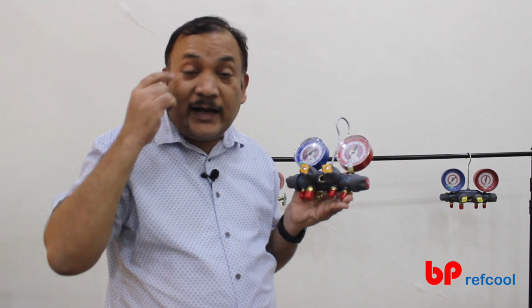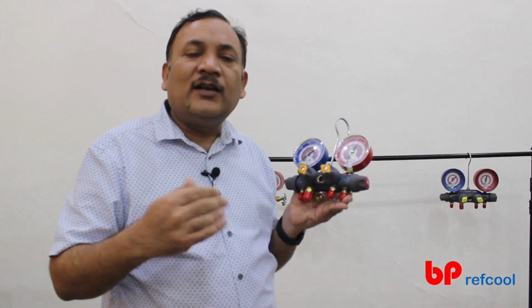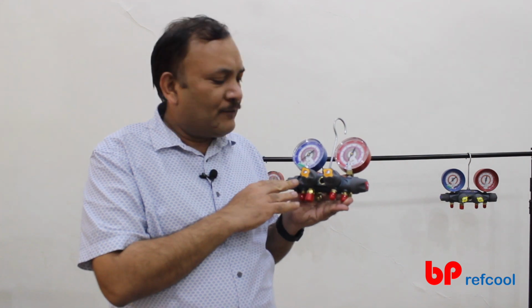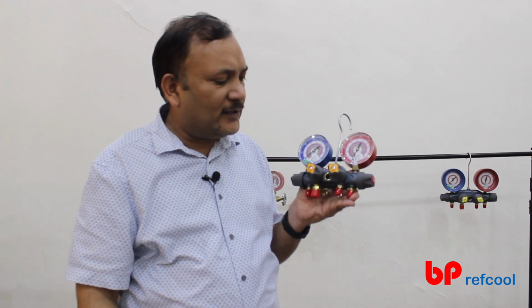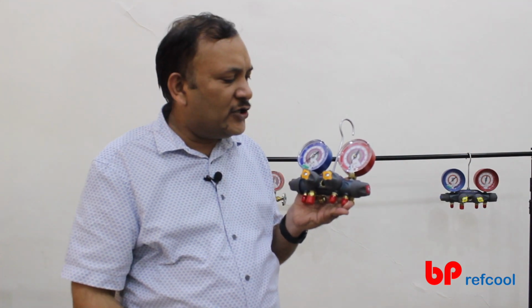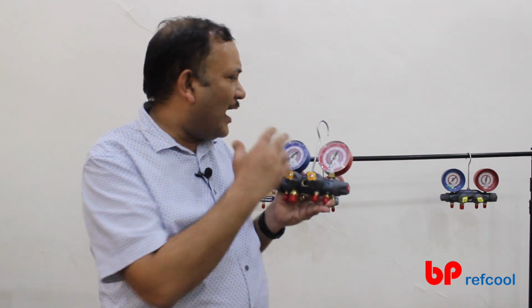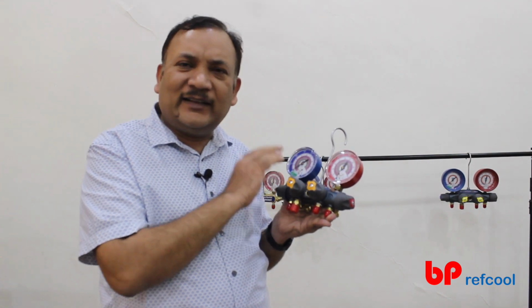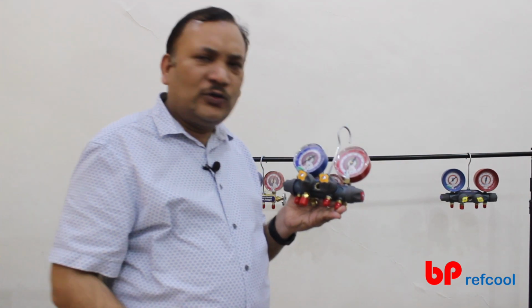So normally if you are doing a charging of a VRF system or any system where you know that any kind of air or moisture is a real challenge for you, you look for this kind of system wherein you manage that there is no air or moisture getting added while commissioning in the process. So that is where this is used. So all chiller applications, all VRF applications, all the places wherever you have both the suction and the discharge side ports, normally people prefer to use this type of manifold gauge, Titan series 4-way manifold gauge with all the features, which comes very similar to what you have. For these there are multiple combinations of which gases and all those things are available.